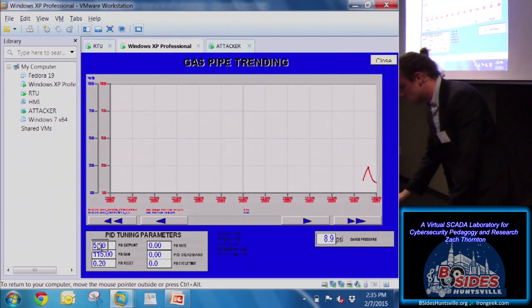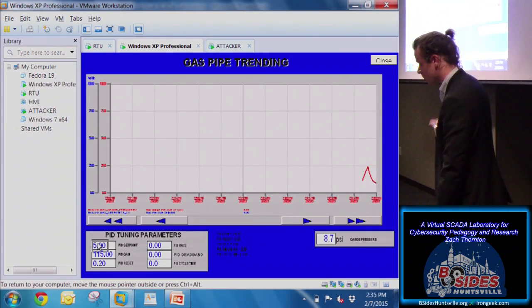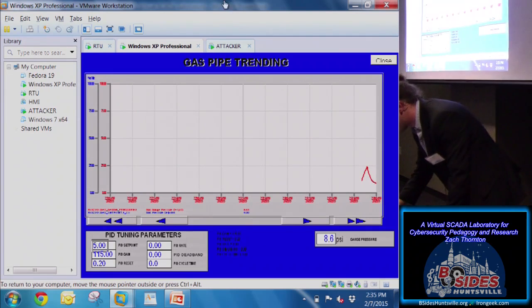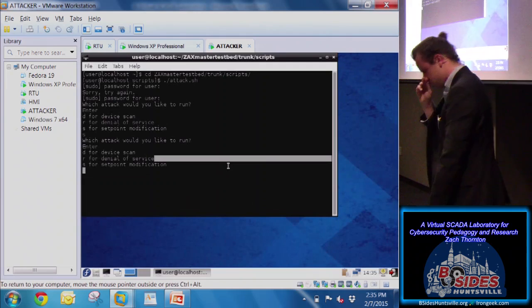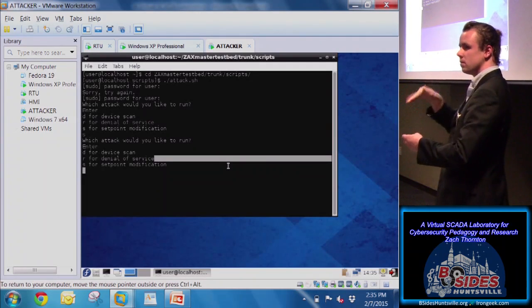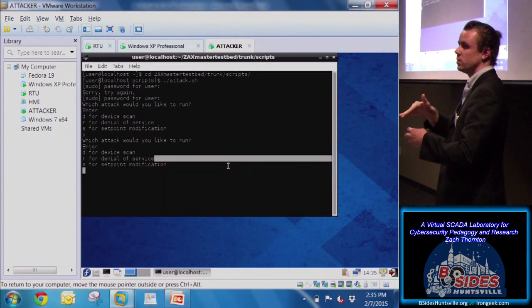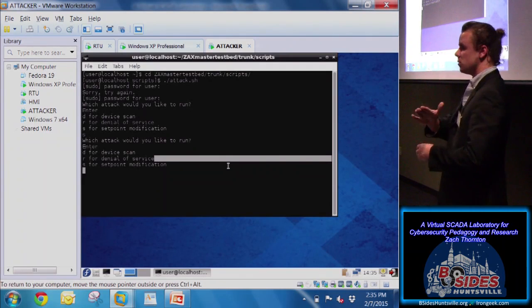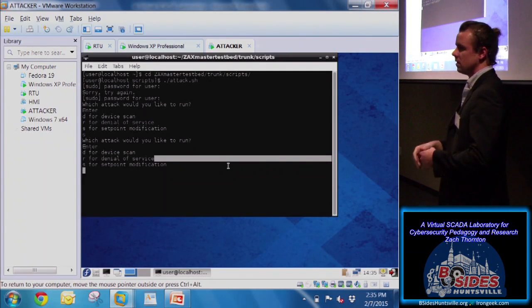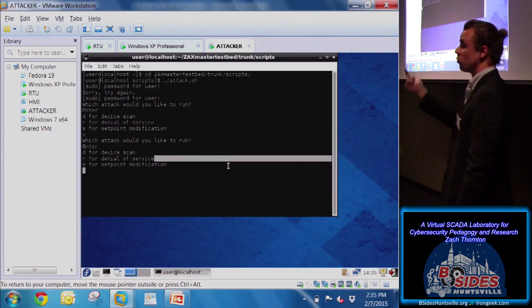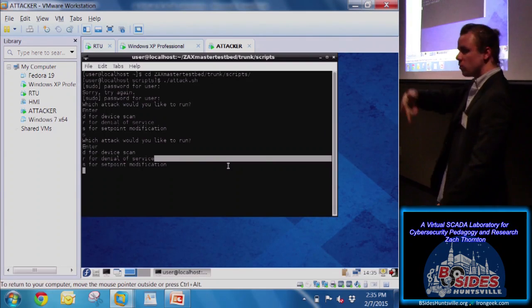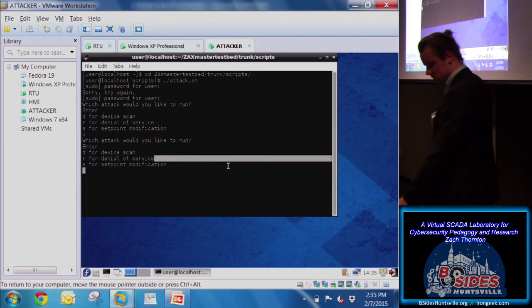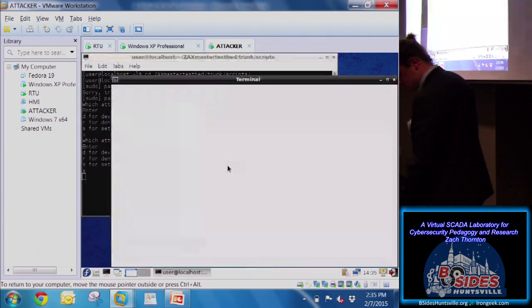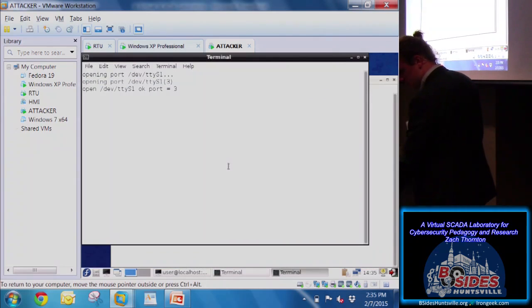What I'm going to do when this returns to normal is attack from a completely different device. I'll basically spam the virtual PLC so that everything the HMI was trying to write, the PLC doesn't hear anymore. Then while spamming with real Modbus traffic, I'll tell it to rewrite the set point.